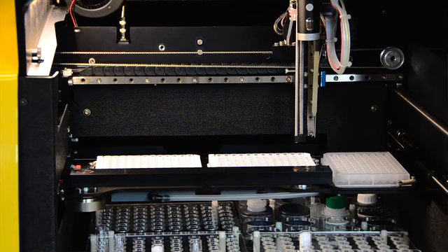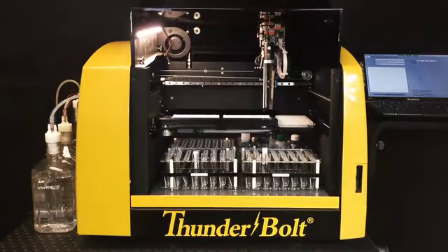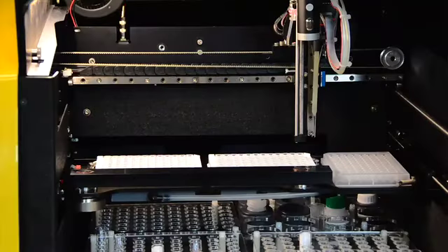Our intelligent rack system allows you to customize your sample load. So if you are a left-handed person and you'd like to start loading your samples from the left, you can. If you'd like to start from the right, you can start loading samples from the right. It also means that you're going to positively identify all the samples that need to be run with the test. It does not matter where they go, they will always be assigned to that test. Now, once again, you can also turn that feature off if you don't want it, and you can load it just like any other instrument would normally have to be loaded.